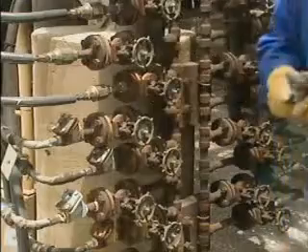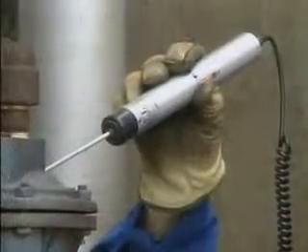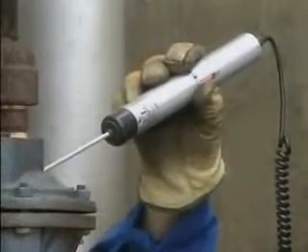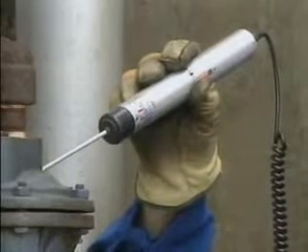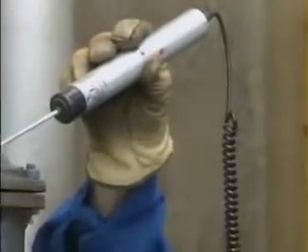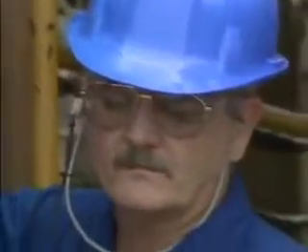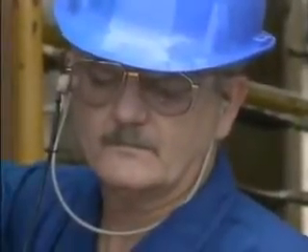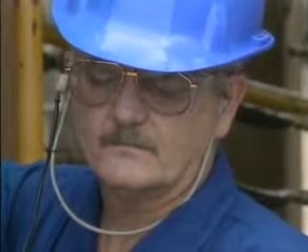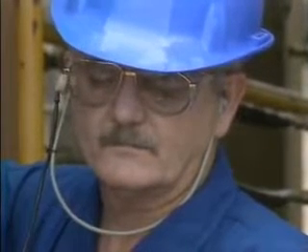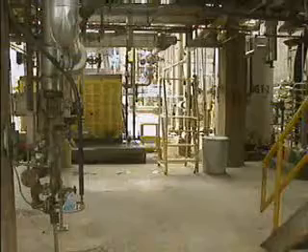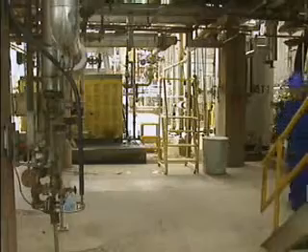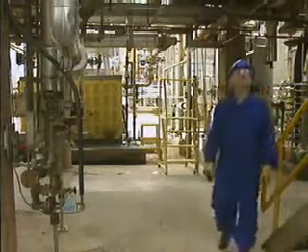Also, when an ultrasonic detector is used to inspect a steam trap, the frequency response of the detector may vary by model and manufacturer. These variations can affect the actual sound that you hear from a trap. But listening to a few examples of typical trap sounds will give you some guidelines that you can apply on the job. A visual inspection can be a very informative part of a steam trap survey.